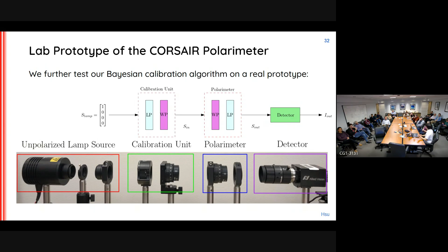Okay. A few others. I think one other small point I want to bring up. We do this test, I think, at 670 nanometers, so red light. The calibration unit has a quarter wave plate at 670. But because CORSAIR has a wave plate that we're going to use at multiple different wavelengths, we don't want to pick one that's at 670. So we picked one at 630. I believe it's a quarter wave plate at 633. So it's a little bit off. So we can actually see if we can get a good test on a wave plate that's not operating at its intended wavelength.